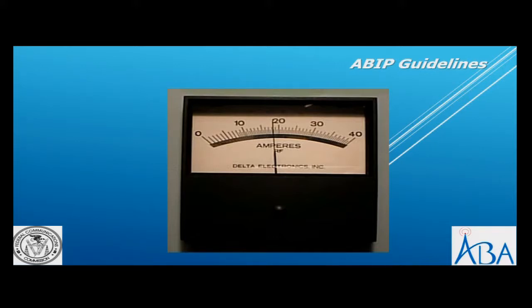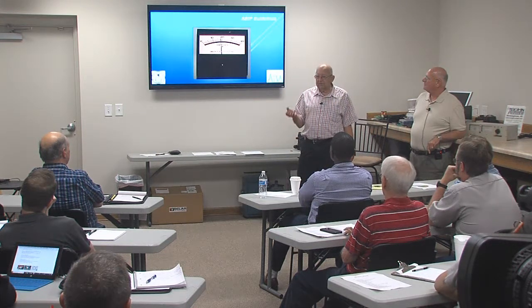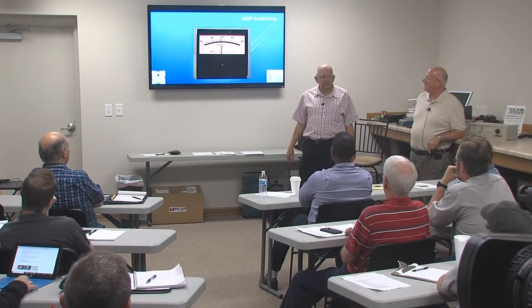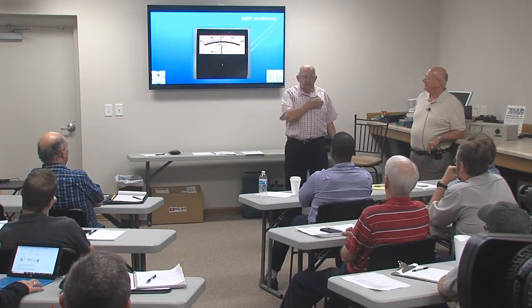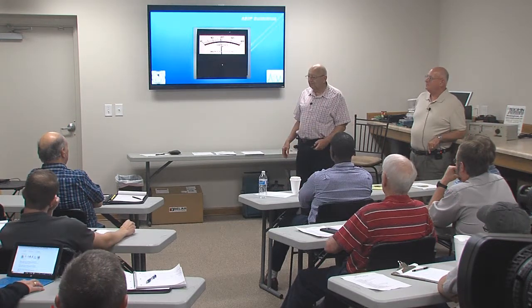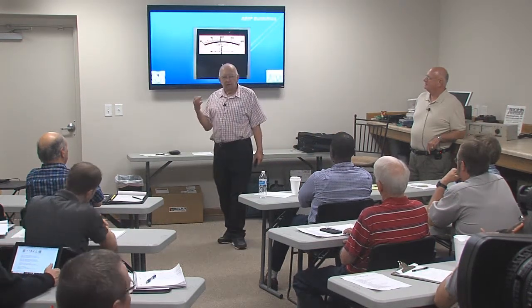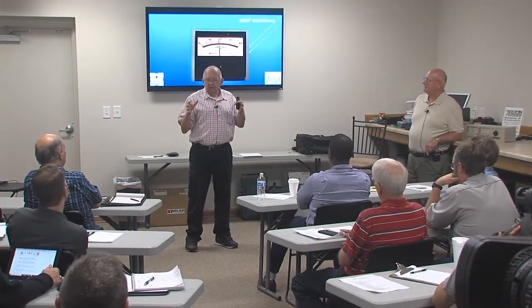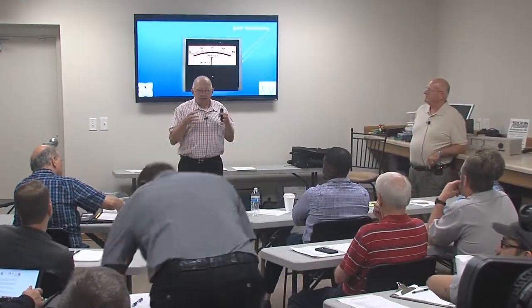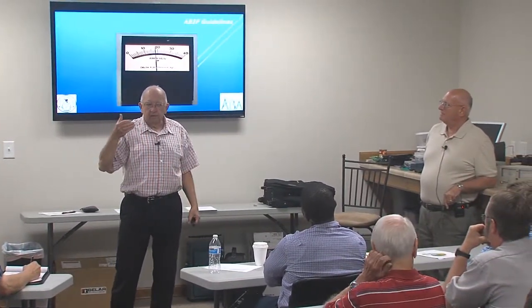Especially on a 50-kilowatt station like Frank's, there's a lot of RF out there. If you start switching switches, even at WSM in Nashville, I was out there one time and before flipping the meter switch, the engineer did it with his pen - he wasn't going to touch it with his hand. In a directional system, you don't typically read the antenna current at each tower; you read it at the common point where the transmitter output goes through a phaser that splits and feeds each individual tower.